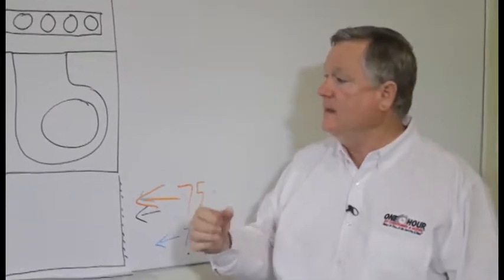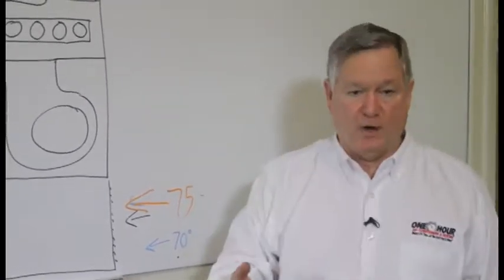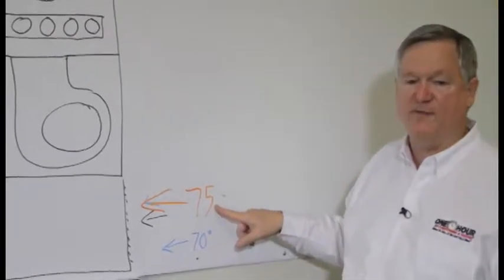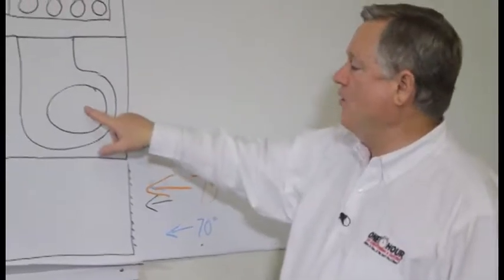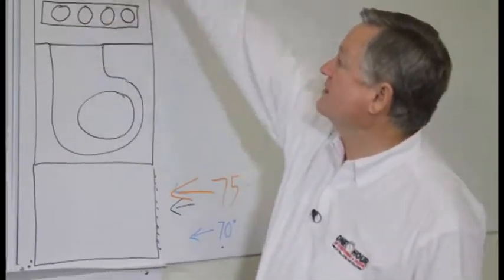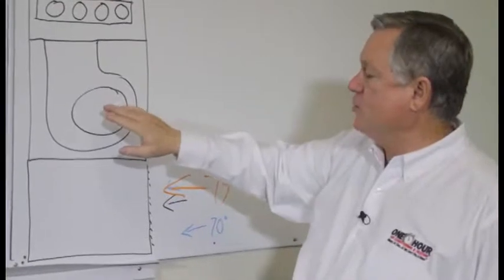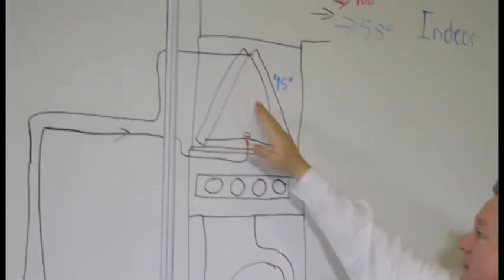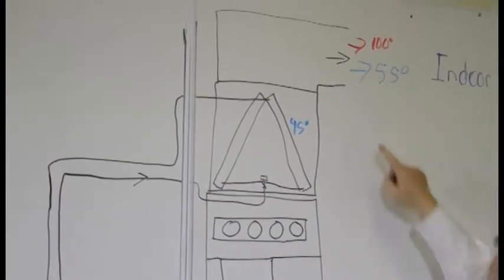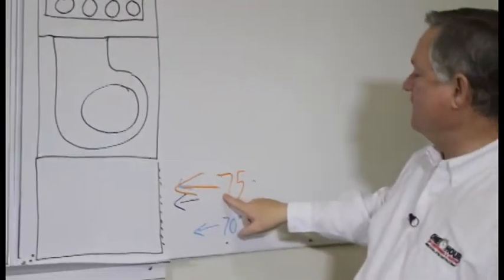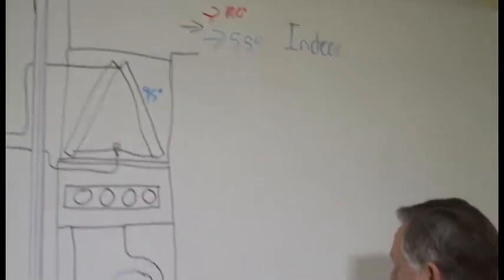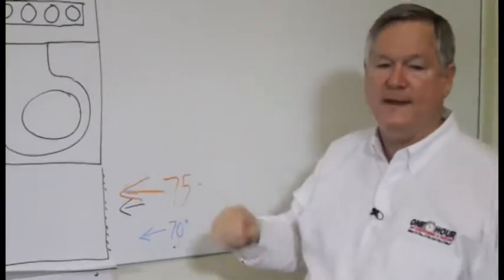in response to the thermostat. Then when you're in cooling mode and you need to refrigerate your home, the air may be coming back at, say, 75 degrees. The same blower is drawing it through. It's going through the same ductwork. It typically is going to a higher speed, but then there's a separate chilling section, which may be 45 degree chilled coils, which drops the air to 55 degrees. So it came into the air conditioner at 75, came through the blower, came out of the chiller, 55 degrees. That comes through your home, chills the home, refrigerated air.